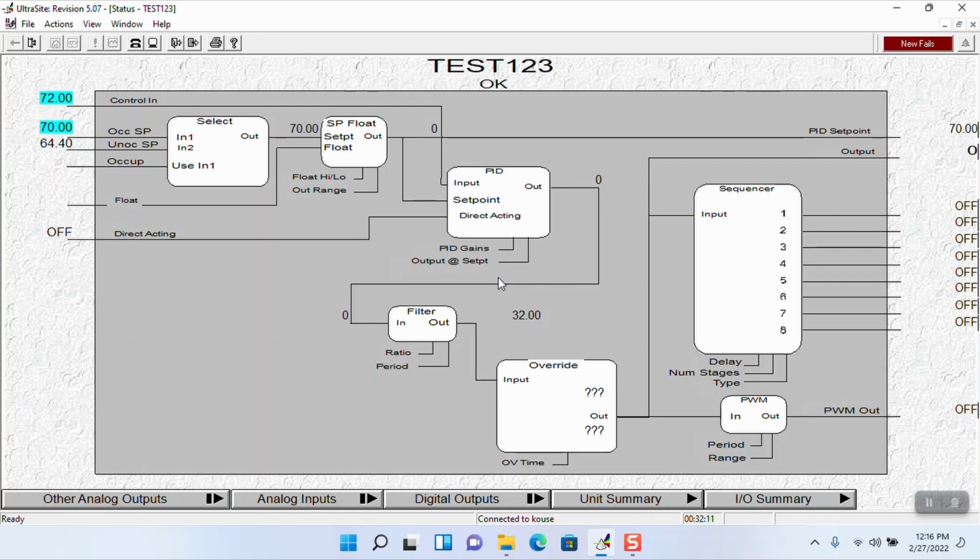For example, Dixell: you have a TR range and you have an I value. You have no P value. Your TR range is your P value in Dixell. And it's backwards. The higher the number, the slower it goes. The lower the number, the faster it goes. Whereas in Emerson's loop sequence controller, or the suction group, the condenser, or the ESR valve, the lower the PID loop, the slower it goes.